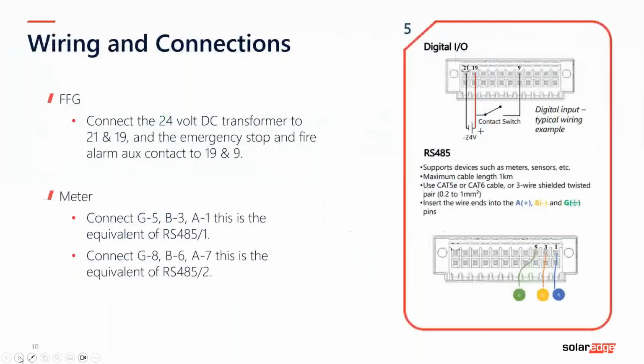The top one we're looking at here is for the Firefighter gateway, or the Firefighter feature. You need a 24-volt transformer with a 1 amp supply. I've colored it in now because our manual isn't very good, it doesn't actually show color coding. The manual was slightly wrong because it has the plus on the left. Plus should be on the right, basically.